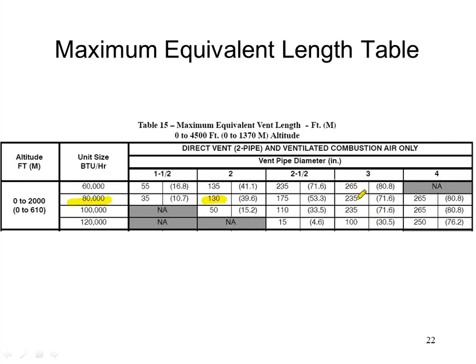If I want to run 3-inch, I can go 235 feet, 4-inch, 265. Right? So these are the different tables you can have. If I have a larger furnace, 100,000 BTUs, it's telling me you can't do it in 1.5-inch pipe. You can do it in 2-inch, but you can only go 50 feet. You can do it in 2.5 for 110, 235, 265. Although I don't think anybody's going to be buying 2.5-inch pipe, but nonetheless.